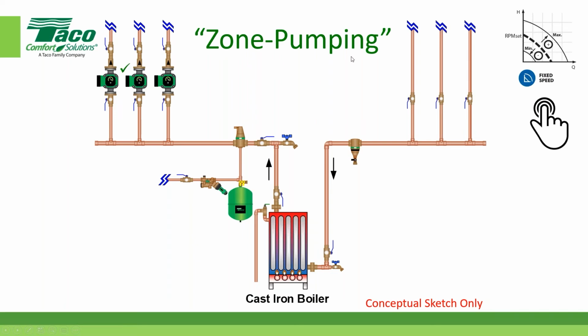So zone pumping is an appropriate mode to operate when I have nothing downstream to give me any feedback. Remember, the feedback to a delta P pump is pressure changes. If I don't have any zone valves out here, or nothing's really going to change in a zone pumping application, I'm not going to get that feedback. That means that unit's never going to automatically do anything. So don't put it on an automatic mode. You may not get enough, or you may pump more than you need. So again, put zone pumping down there as an appropriate fixed speed.